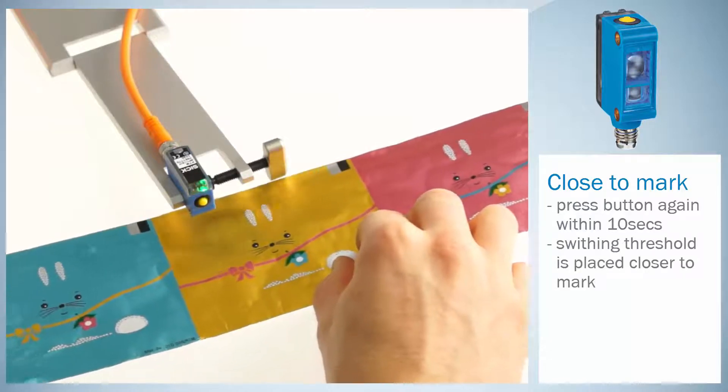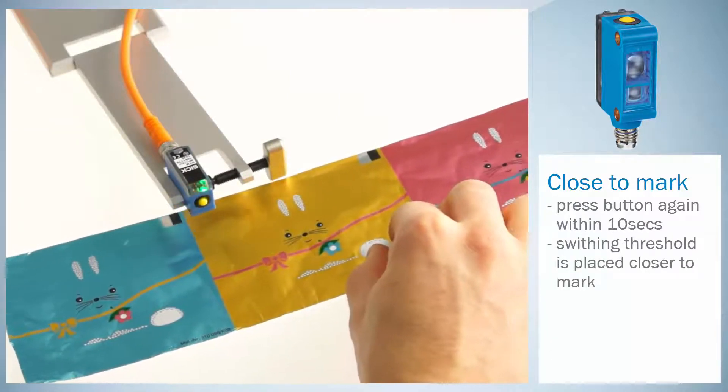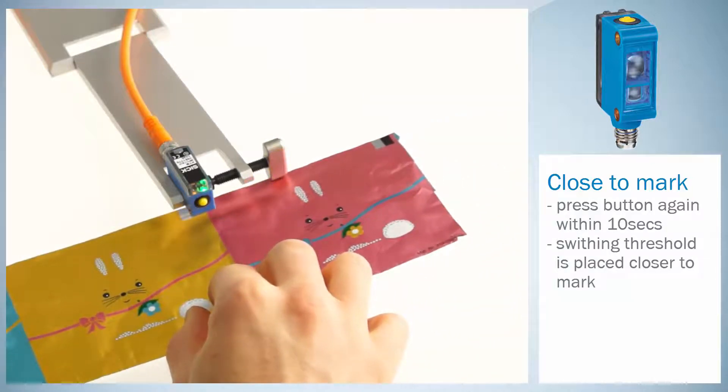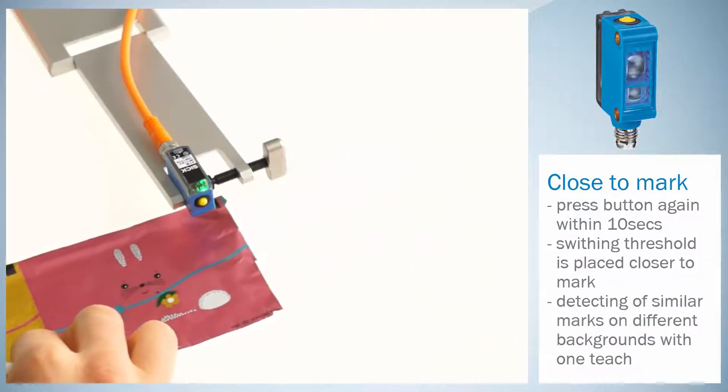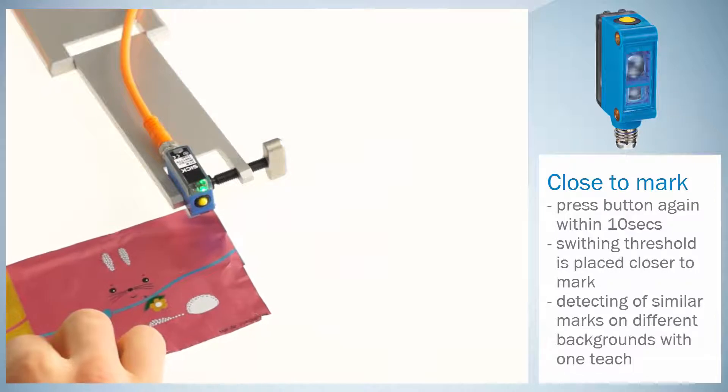This means that the switching threshold is placed closer to the mark instead of in the middle between mark and background remission. This feature allows detecting similar marks on different colored backgrounds with one teach.